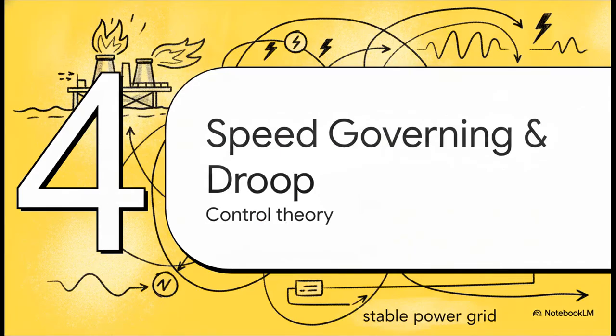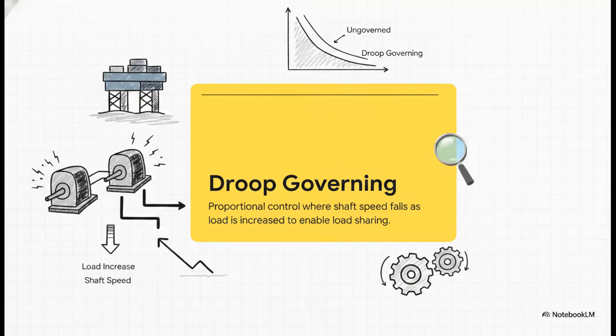So how do we handle this? Let's get into part 4, speed governing and droop. How do we actually control this volatile, heat-sensitive beast to keep a stable power grid? We use droop governing. This is honestly the most reliable method for accurately sharing electrical load among multiple generators without causing cascade tripping. See, an ungoverned gas turbine has an incredibly steep, unstable speed-to-torque ratio. Droop governing introduces proportional control.